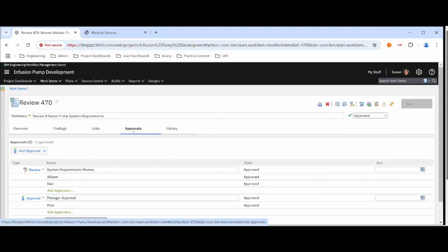It's very important that we see who is approving it, when it was reviewed, what the approvals are, because these are medical devices, and one of the design requirements from the ISO standards is that you have a traceability of what requirement was reviewed and who reviewed it and who approved it and so on.